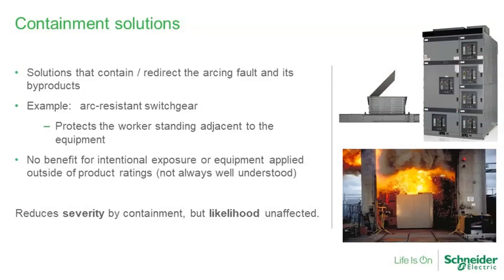Basically, what I'm talking about are solutions designed to contain or redirect the arcing fault and its byproducts. What I'm talking about here is really arc-resistant switchgear. The idea with arc-resistant switchgear is that even if an arc occurs inside of it, you protect the worker who's standing adjacent to the equipment. Now they may still be scared when the explosion happens inside, but at least their clothing, ideally, is not going to be caught on fire. They're not going to wind up in the hospital with burn injuries.